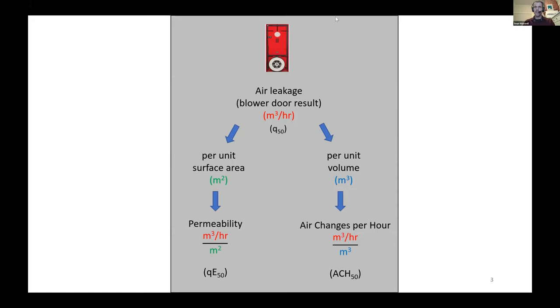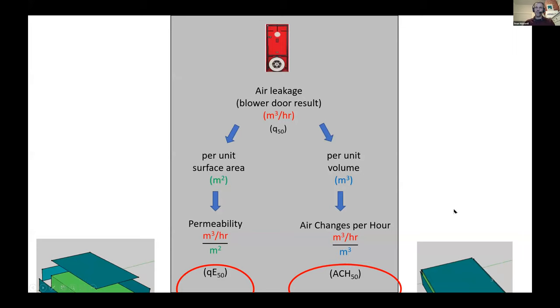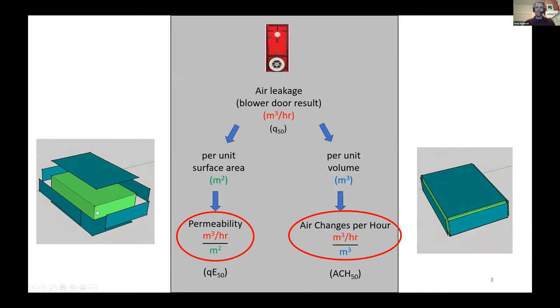But what you'll hear sometimes is ACH or ACH 50. That's air leakage per unit of volume. And so I just put these pictures in here to give you some sense of what I'm talking about. When I say surface area of one of these buildings, I'm talking about the surface area of the walls, the floor, and the ceiling of this box or building. So for a house, that includes the floor slab. For a building, that includes the floors, and it also includes the walls and the ceiling, the entire conditioned envelope. So that's some basic terms there, ACH and permeability.